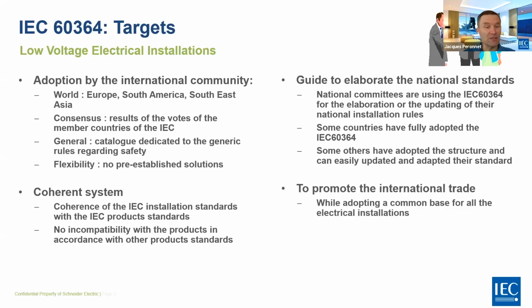This standard is based, as any IEC standard, on consensus. And this is the result of the vote of the national members, which make the standard. This is something general because it's a catalog of dedicated rules regarding safety. And it's very flexible because there is no pre-established solution. So this is the main difference between the code that you used to have and this standard, which is really very flexible, without any pre-established solution. This is a coherent system. So we have a coherent installation standard with the IEC product standard, and also no incompatibility with products in accordance with other product standards.